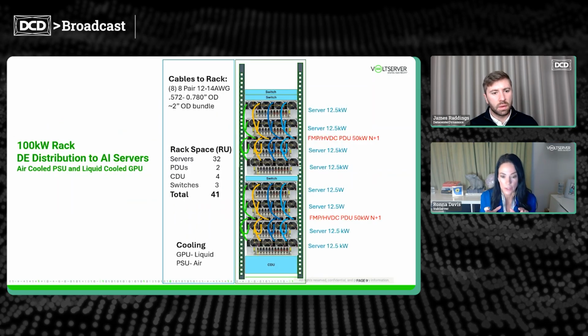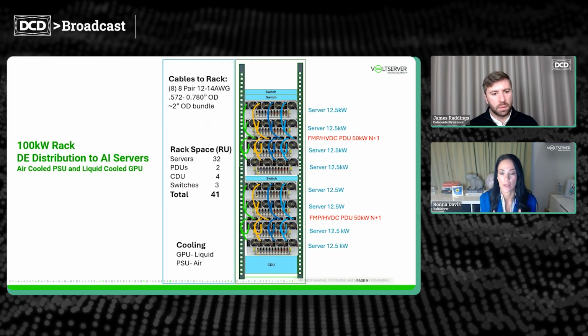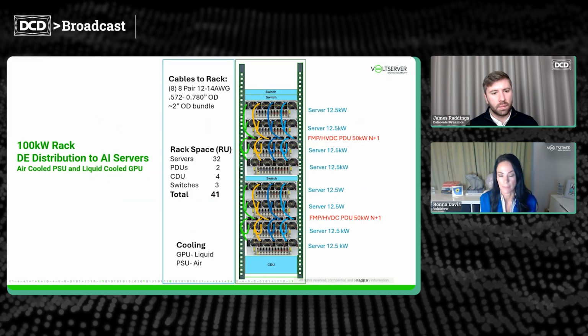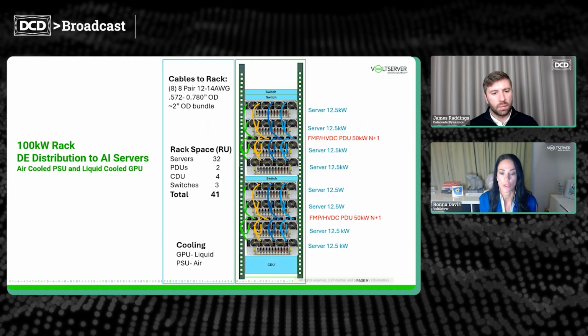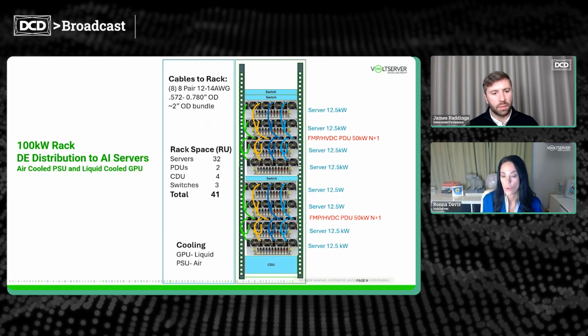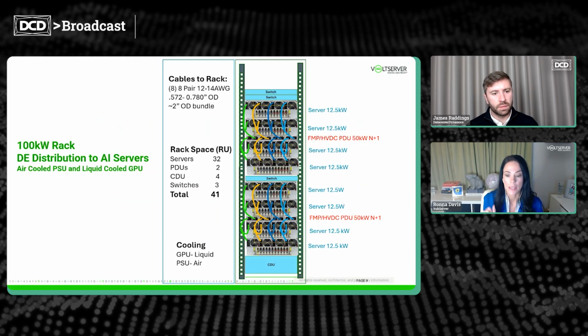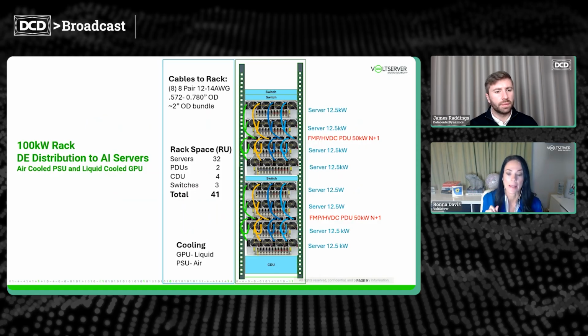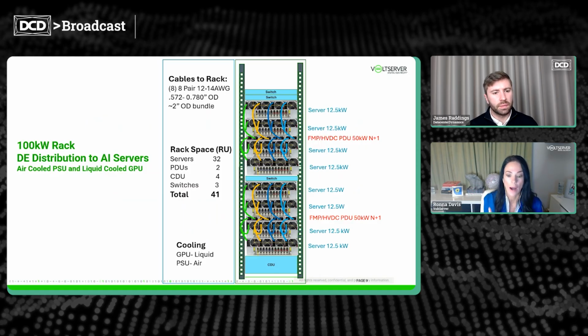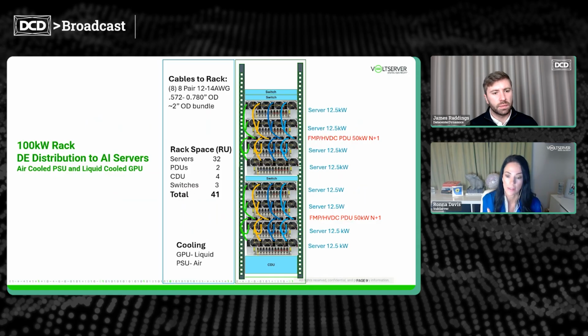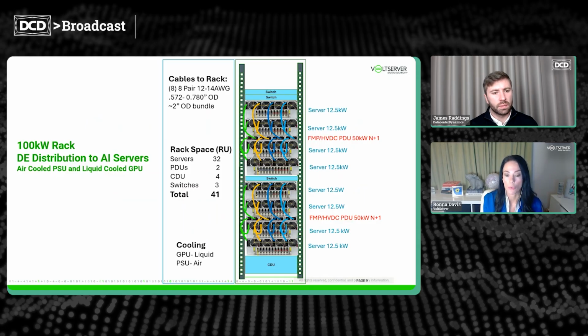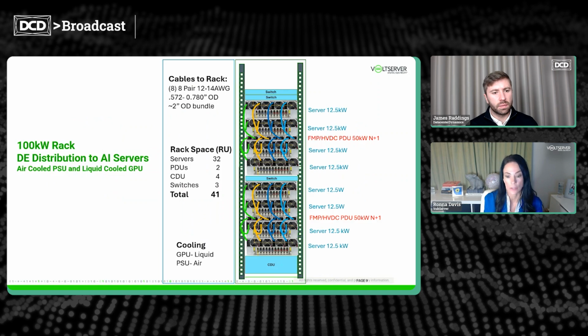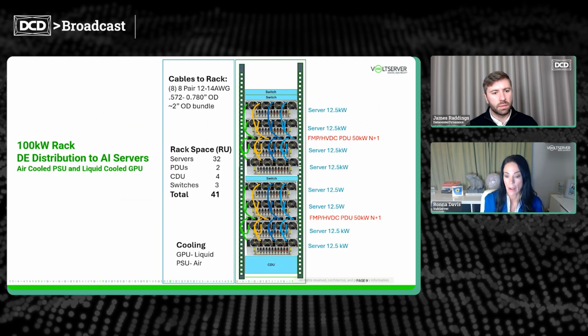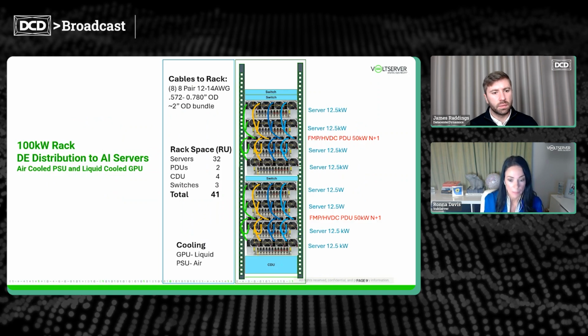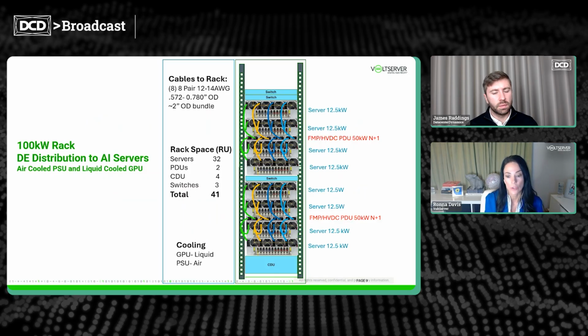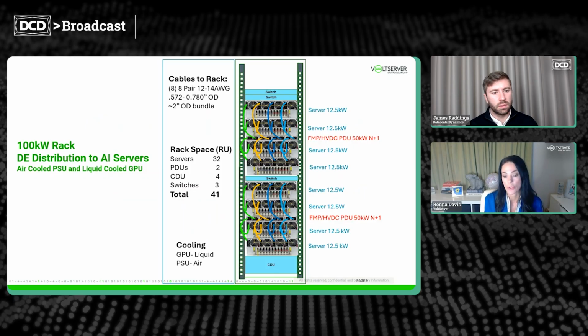So now we're going to look deeper inside. We're going to look at that 100 kilowatt N+1 server cabinet and how that power is distributed to the AI servers. We have 2 PDUs, each with 4 power sleds, and each power sled has 2 high voltage DC power outputs. Each of those outputs supports 2 AI server power supplies with a Y-style power cable. You'll have plenty of space for your power cords, and importantly, you'll also have room to distribute the liquid cooling lines for your GPUs.